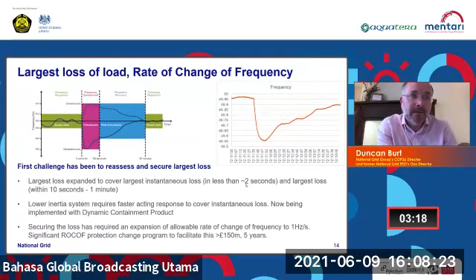Now, that faster rate of fall of frequency and that higher risk on the system means that we need faster acting response to cover that loss, which is being covered by the new dynamic containment product, which is mainly delivered by batteries. As Craig said, those markets are procured competitively and have brought lots of additional fast acting containment plant onto the system. Alongside that, we have a very significant program changing lots of rate of change of frequency protection relays right around the system to expand the acceptable rate of change of frequency from 0.2 hertz per second to 1 hertz per second. Those two measures together, both faster acting frequency containment and the adjustment of protection settings to allow the frequency to change faster, mean that we can continue to secure the system reliably at sensible costs in line with historic, but with a much more flexible system orientated around batteries and other fast control devices.